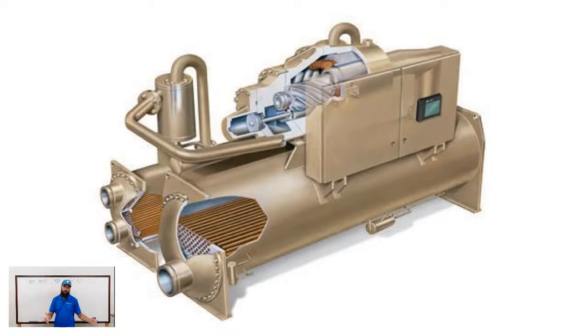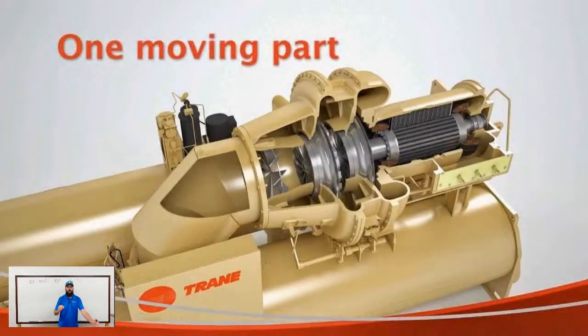We've talked about screws fairly heavily. Let's talk about a centrifugal. Almost any centrifugal is going to use a PRV or an IGV. This all means the same thing. IGV is an inlet guide vane. A PRV is a pre-rotation vane. They're literally the same thing, just different manufacturers call it different things, such as VRV versus VRF. As far as I'm aware, York is the only one that uses the PRV terminology.